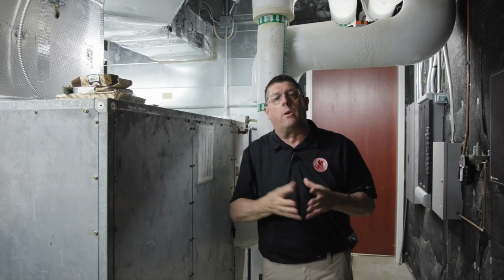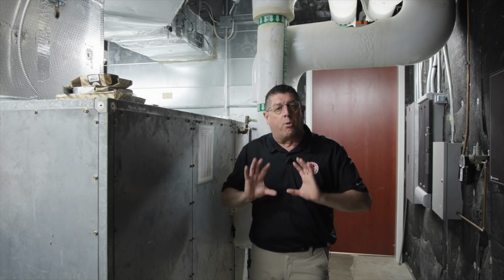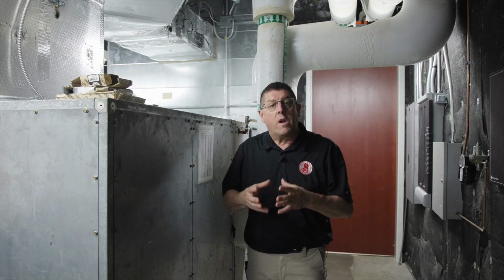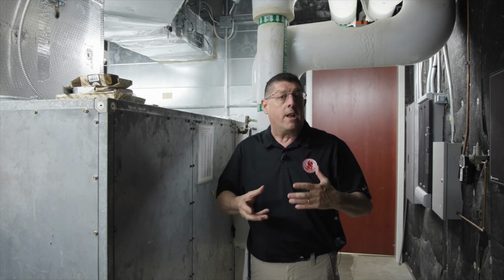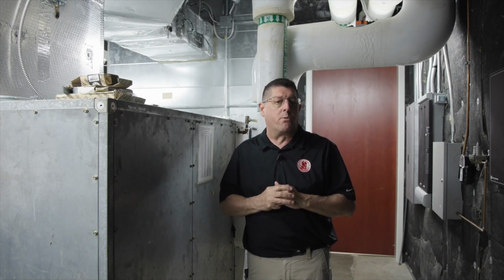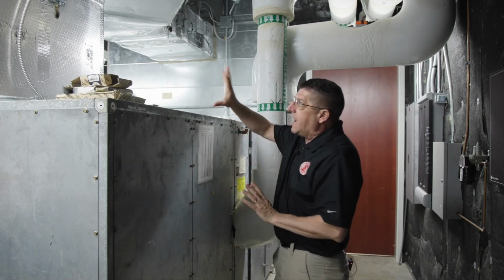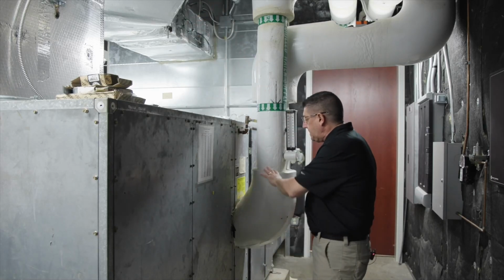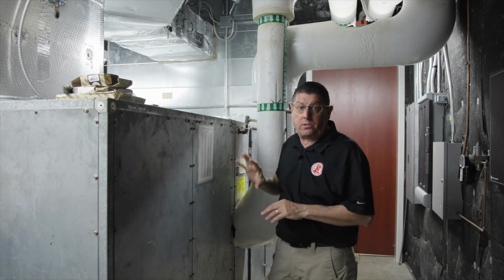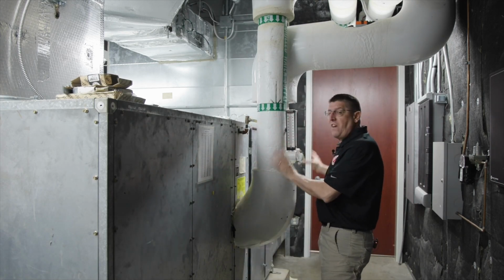In the same principles you have with normal residential forced air units, we know that we can push air 5, 10 feet, but we can draw air 20, 30, 40 feet. It allows a better convection of airflow through a building. So in this particular installation of this air handling unit, I've got the supply air being pushed up. Remember, that's that air that's been comforted with the cool. And on the back, I've actually got return ducts because I'm actually drawing air back by this large fan unit.